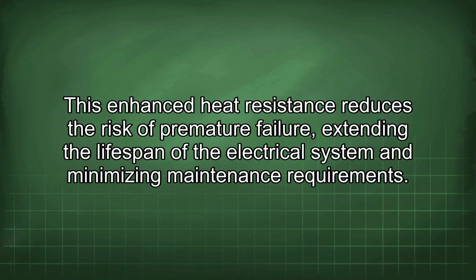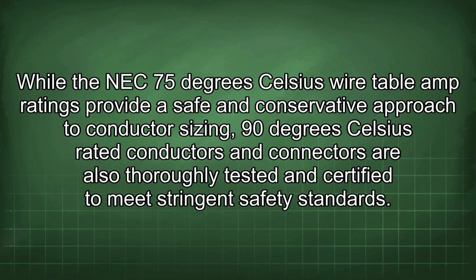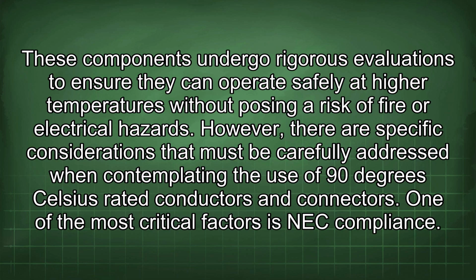maintenance requirements. While the NEC 75 degrees Celsius wire table amp ratings provide a safe and conservative approach to conductor sizing, 90 degrees Celsius rated conductors and connectors are also thoroughly tested and certified to meet stringent safety standards. These components undergo rigorous evaluations to ensure they can operate safely at high temperatures without posing a risk of fire or electrical hazards. However, there are specific considerations that must be carefully addressed when contemplating the use of 90 degrees Celsius rated conductors and connectors.